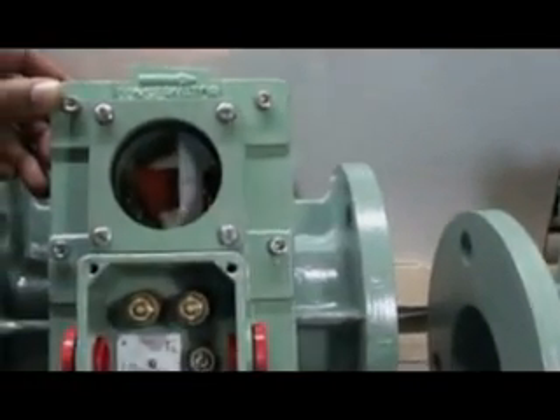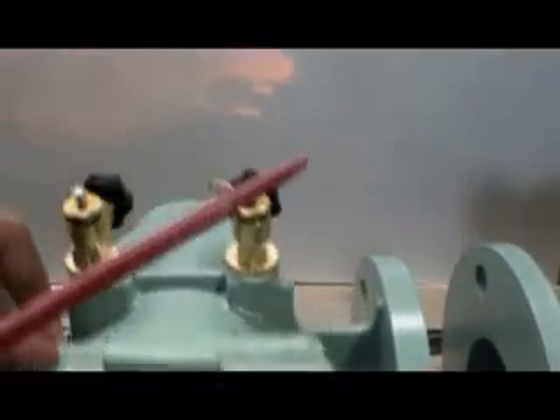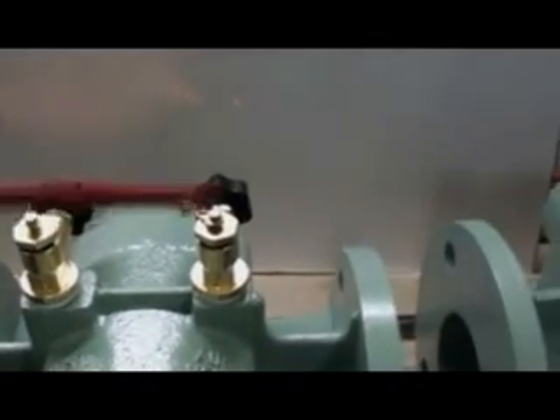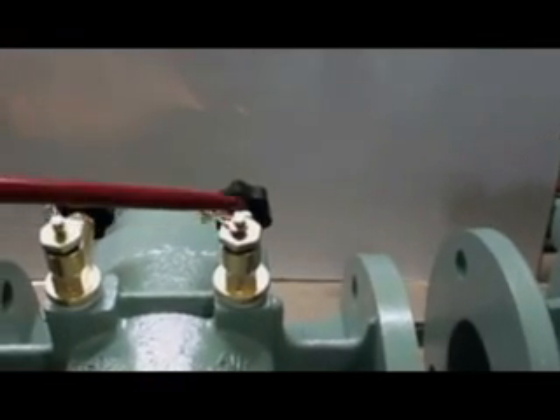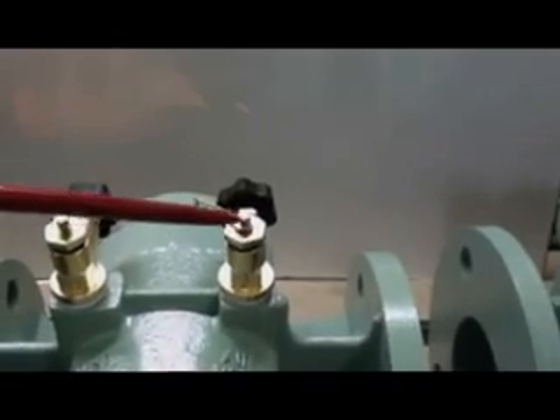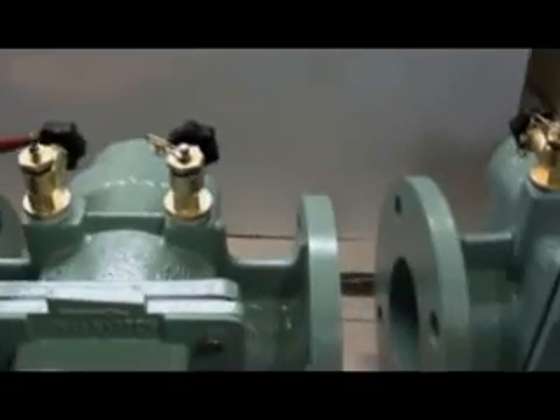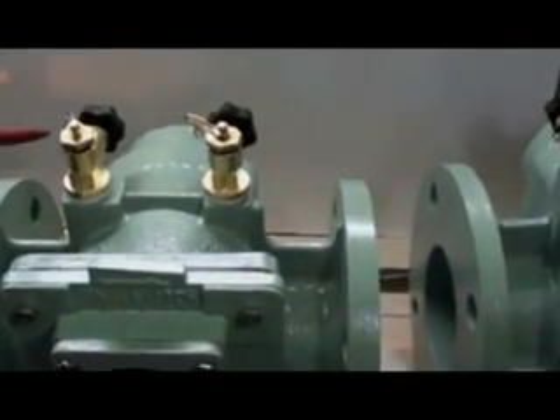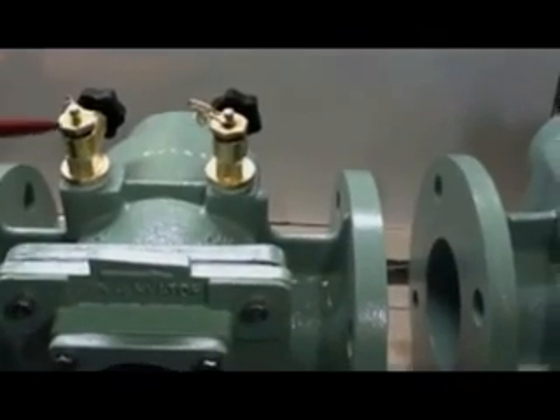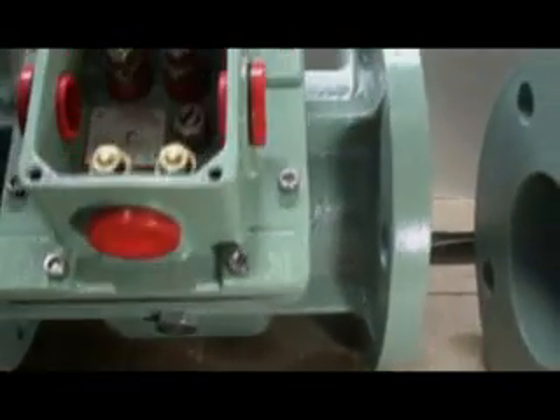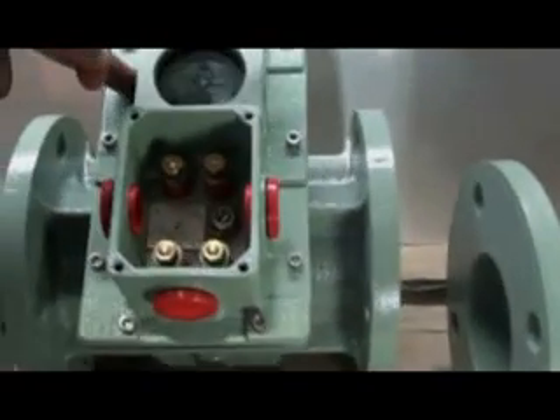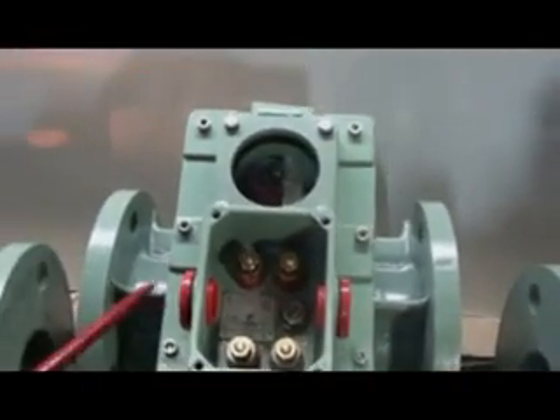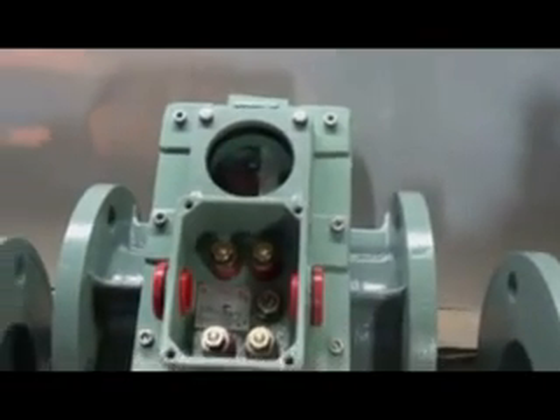On the top of the Buchholz relay, there are 2 petcock valves. Right side is for air venting and left side is for test vent of Buchholz relay. We can compress air from left side valve and check the operation of Buchholz relay. In the bottom, there is a plug arrangement. This is used for draining the oil from Buchholz relay.